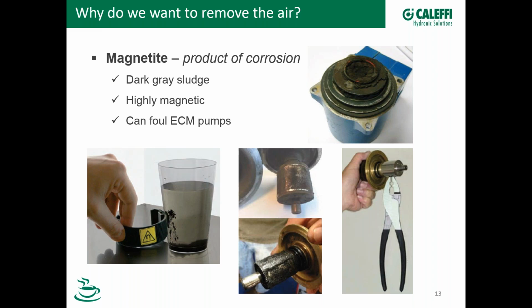We show here, see that pliers hanging from that ECM magnet on the right, and you can see the collection of that magnetite material on that rotor. And that material is sometimes also called boiler ink. It's black and almost looks, it sticks to your fingers too. So this is a product of corrosion and also caused by air.